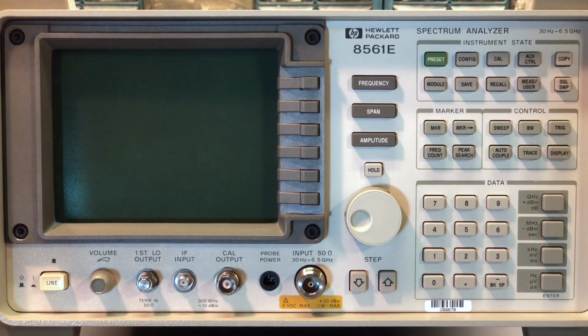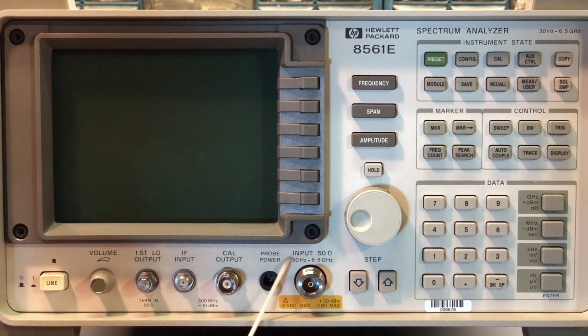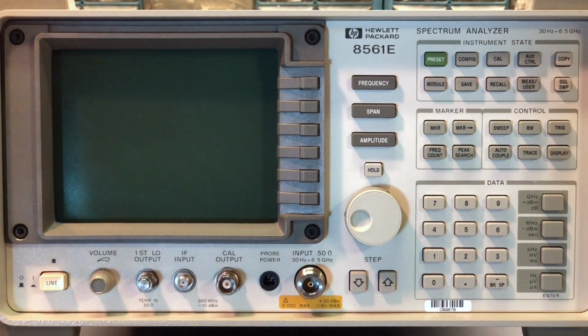So when this is DC coupled, it will extend from 30 Hertz, or that lowest frequency of 30 Hertz. When this is AC coupled, the lowest frequency, I believe, is about 100 kilohertz. So you do lose some of that low-end frequency. So if you need to extend to 30 Hertz, you do have to DC couple the instrument. The AC coupling is the default setting because it is safer. It blocks any accidental DC voltage from getting into the instrument.